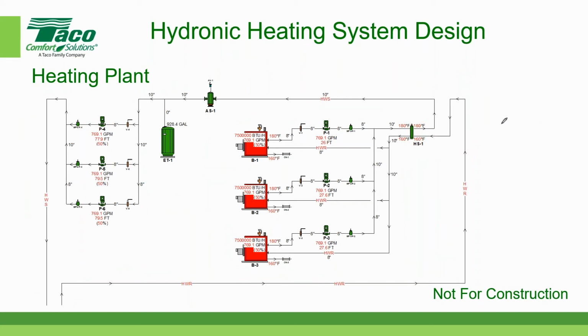All right, so now let's look at some of the components more carefully and see what we've got here. So on the primary side, let's just look at one boiler at a time. Now, again, as I have down here, it says this is not for construction. The intent is not to show every single device in the system, but to give you a general idea of what the arrangement should be. So in this case, we're pumping away from the boiler. Depending on your philosophy, some people like to pump to the boilers. I like to pump away from the boiler. The main reason for that is that if I pump away from the boiler, then I can maintain a reasonable pressure inside my boiler. And also, I want to try to get the hottest water on the suction side of my pump if I can.